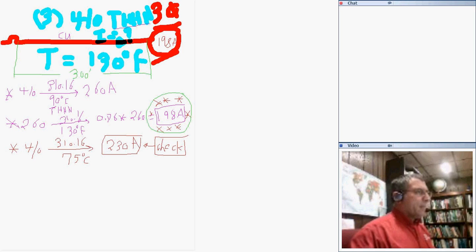This time I will find how much current I can get out of the 4/0 if I pull it 300 feet. I need to give you the voltage, guys. It's 3-phase, and the voltage is 480. If I want to size based on voltage drop, I have to give you the voltage. Let's do that.